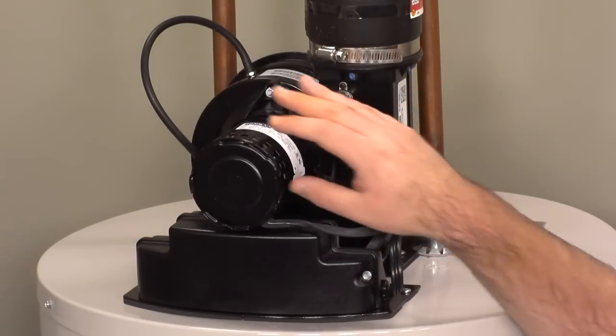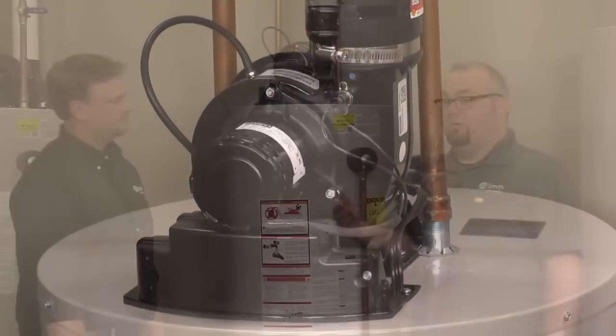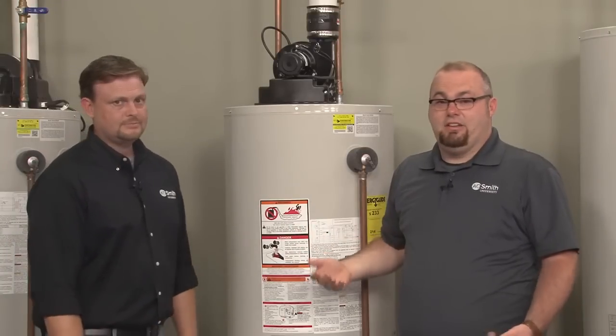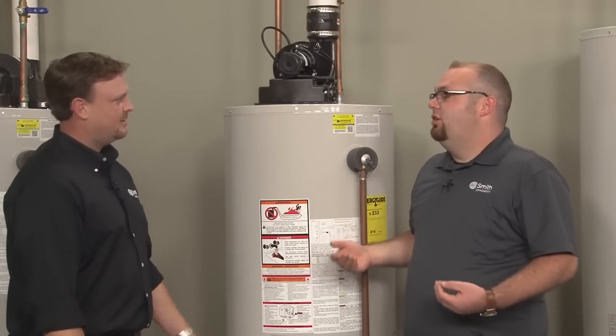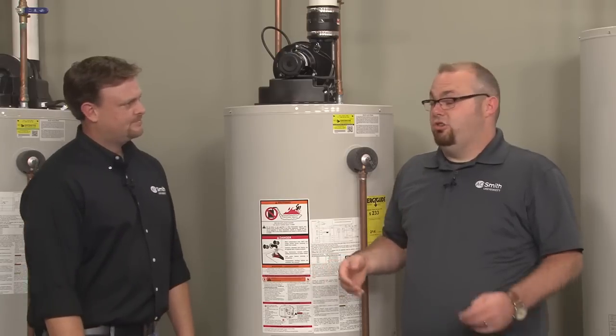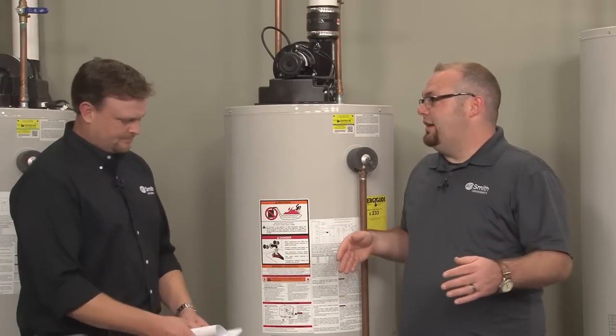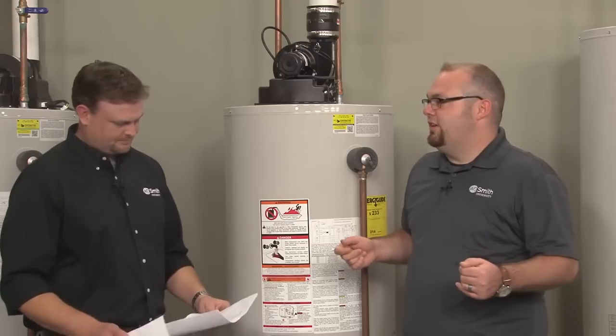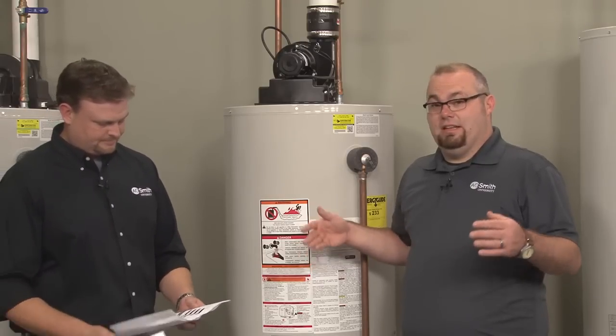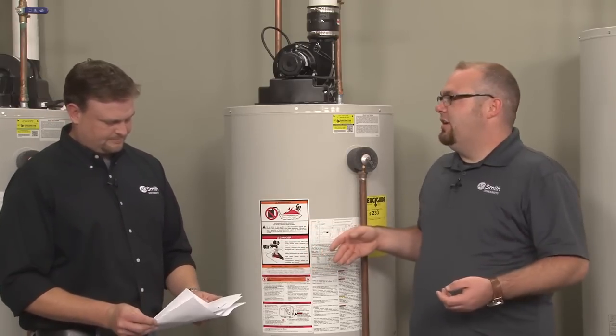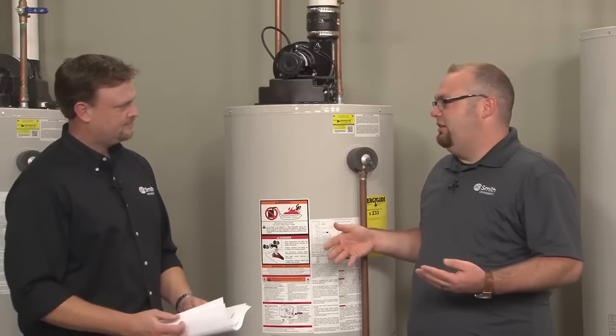So I check the wiring, check the tube. Next thing is one of the most important things. I check the venting to make sure the heater's vented properly per the manual. So make sure your distances between elbows is right. If it states that there has to be a certain distance, make sure your equivalent length is correct, because a lot of people forget that elbows count as feet.